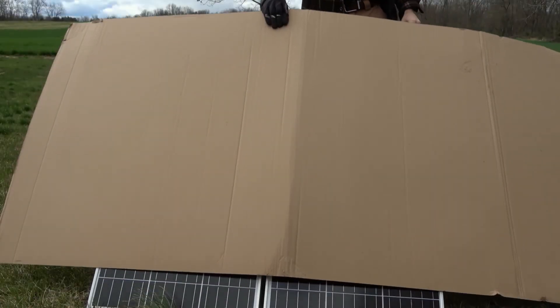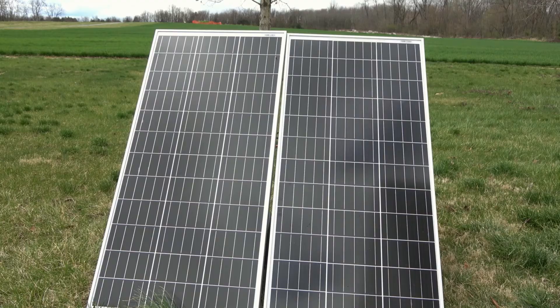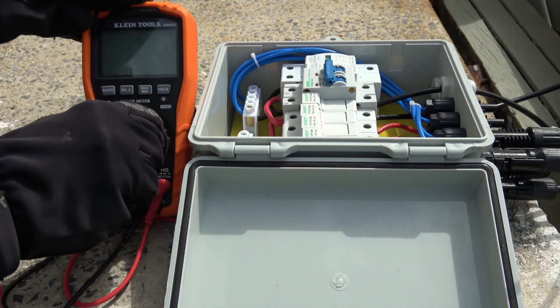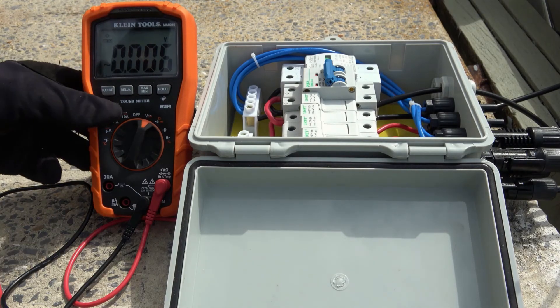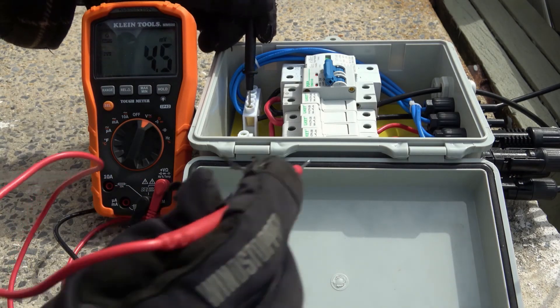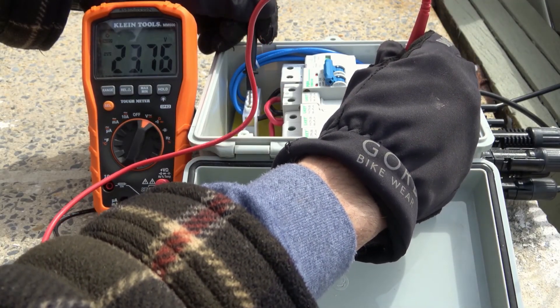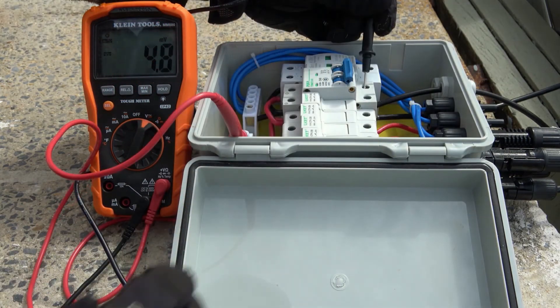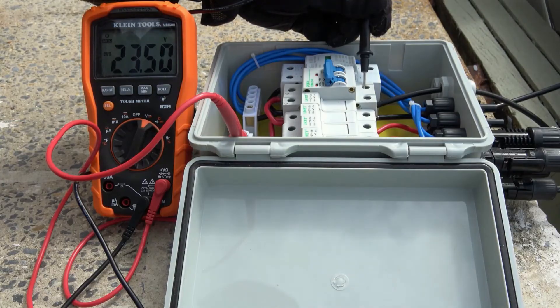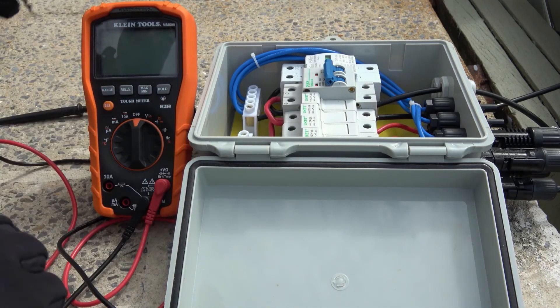Once the output lines have been connected with the rest of the electrical system, we can uncover the solar panels to expose them to sunlight. With the panels producing power, we can measure the voltage and current using a digital multimeter. We'll measure DC voltage by selecting the appropriate voltage setting on the multimeter, connecting the negative lead to the negative bus bar and the positive lead to the positive input. In this case, we have a little over 23.7 volts on the first string and about the same voltage on the second string — so both strings are operating at the same voltage. Turning the breaker back on and moving to the positive bus bar, we measure a combined output of 23.5 volts, demonstrating that the voltage remains unchanged in a parallel configuration.